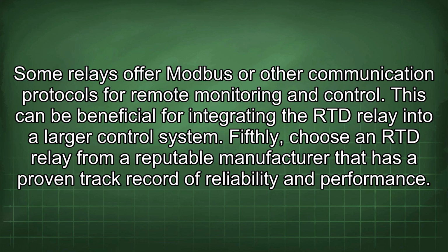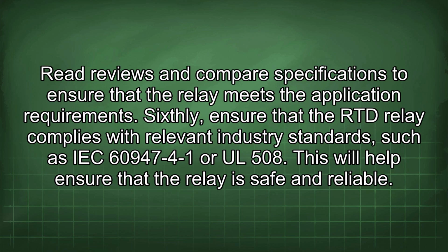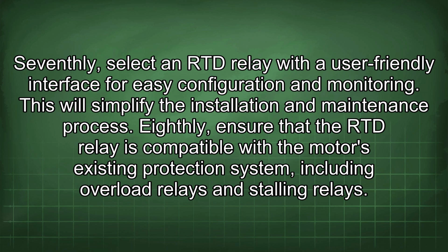Fifthly, choose an RTD relay from a reputable manufacturer that has a proven track record of reliability and performance. Read reviews and compare specifications to ensure that the relay meets the application requirements. Sixthly, ensure that the RTD relay complies with relevant industry standards such as IEC 60947-4-1 or UL 508. This will help ensure that the relay is safe and reliable. Seventhly, select an RTD relay with a user-friendly interface for easy configuration and monitoring. This will simplify the installation and maintenance process.